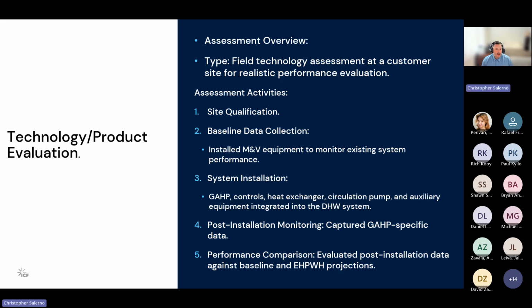So the technology and product evaluation, so kind of what we did to implement this field study at this site was, obviously we did an assessment at a customer site for a realistic performance evaluation. But firstly, we did site qualification. It was a little challenging to find a good site where the DHW load was sufficient to be able to keep the gas-fired heat pump running as much as it can, but also finding sites where the central domestic hot water heating systems are accessible and can be easily retrofitted with these technologies. So as you may be aware, gas-fired heat pumps need to be outside. So being able to retrofit these into systems requires running piping to and from outside where you would install it in a location that meets codes and is appropriate.